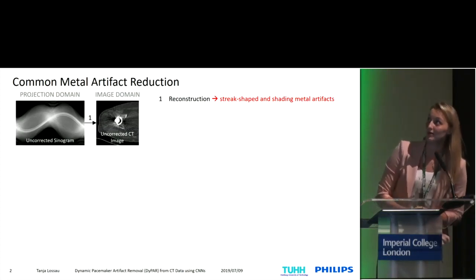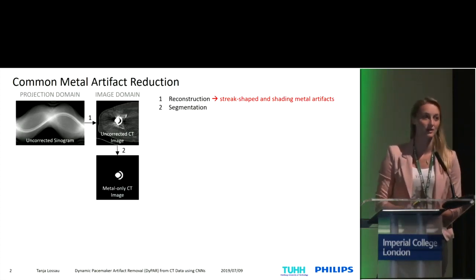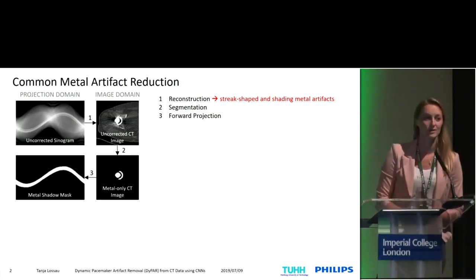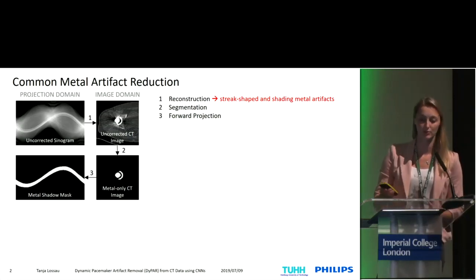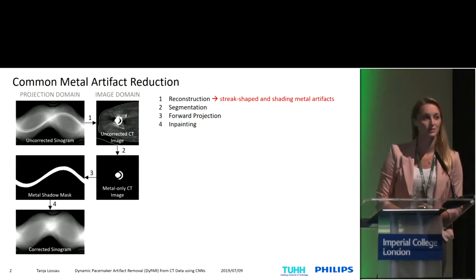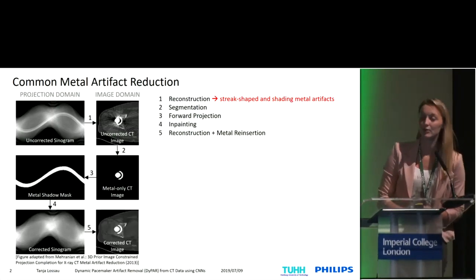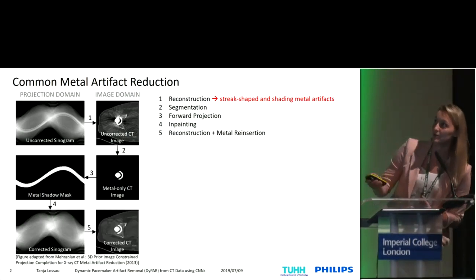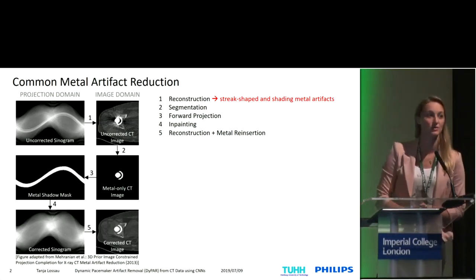In common metal artifact reduction pipelines, the next step is a segmentation of the metal in the image domain. When we do a forward projection, we can identify line integrals which are metal-affected in the projection domain. These are treated as missing data, so we can perform an in-painting to yield a metal-free sinogram. When we do a reconstruction, we obtain a corrected CT image without metal artifacts and can then reinsert the metal based on our metal-only CT image obtained in step two of this pipeline.